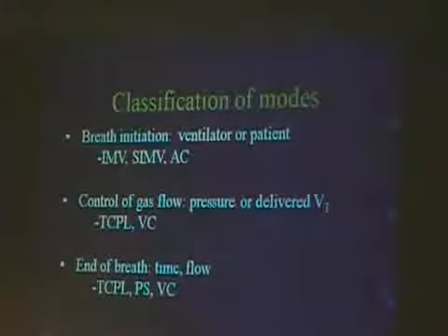What controls the flow of gas? The pressure or the delivered tidal volume? Most people use time cycle pressure limited ventilation, which means it's a pressure mode. And there are some reasons for that I'll briefly describe. In the newborn, we usually don't use volume control. It's a very difficult mode.